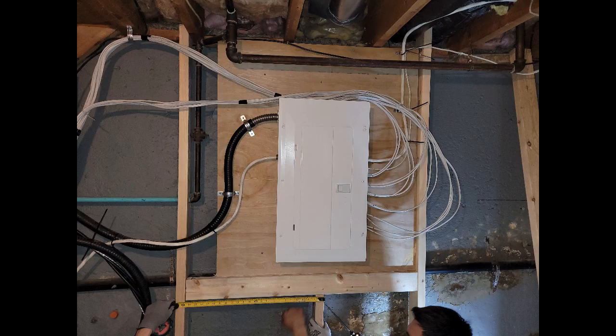And you can see the first two wires, 1 and 2, work here, so it will be like 1, 2, 3, 4, 5, 6. We have like 13 wires here in total, so that will give us a lot of room to work with. I don't know if you guys can see here, this neutral wire is squeezed really badly here. I think when they installed the cable here, they tightened the connectors too much, so they squeezed the neutral wire too much. And that is everything for my panel upgrade part 1 for today.